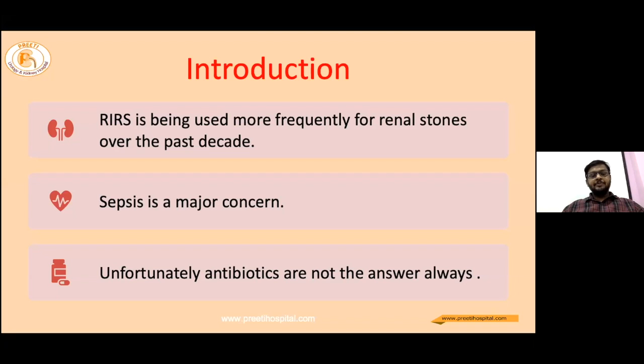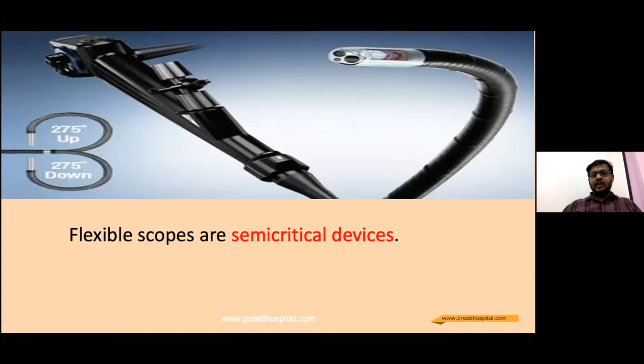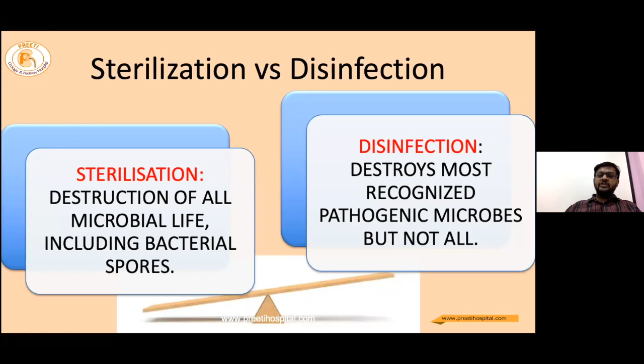RIRS is being used more frequently for renal stones over the past decade. Sepsis is a major concern. Unfortunately, antibiotics are not always the answer. According to Spalding's classification, all our flexible scopes have been classified as semi-critical devices, which require either sterilization or high-level disinfection. As you all know, sterilization is the destruction of all microorganisms, including spores, whereas disinfection destroys most pathogenic microbes, but not all.